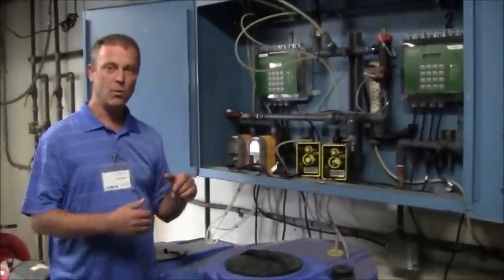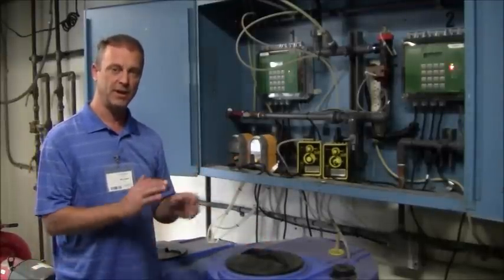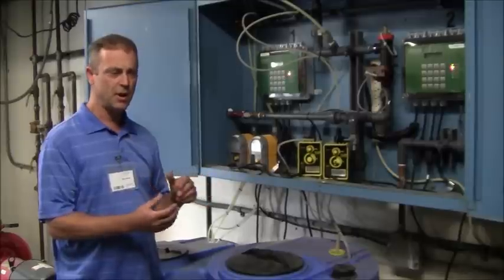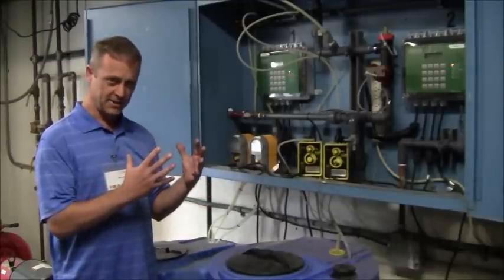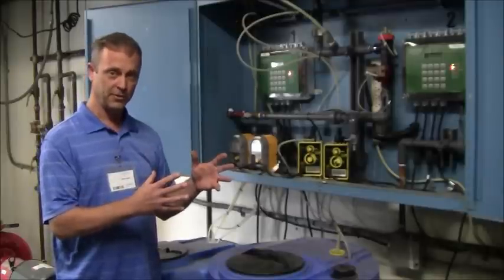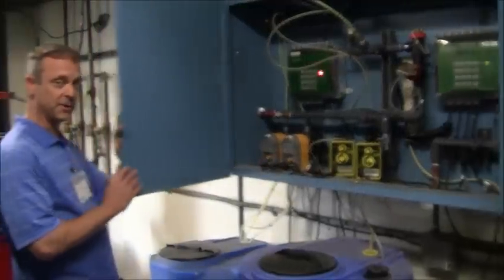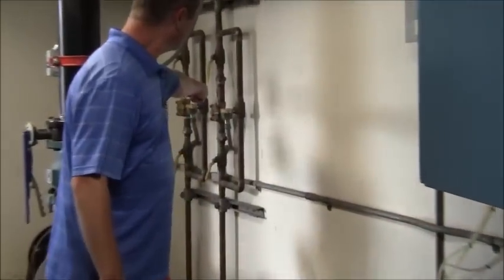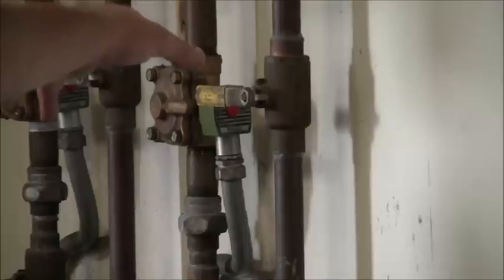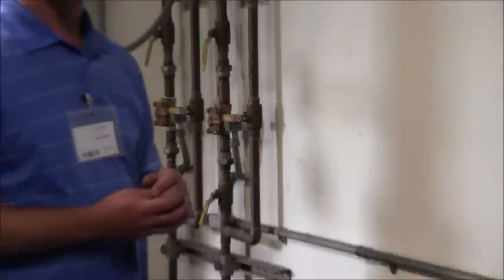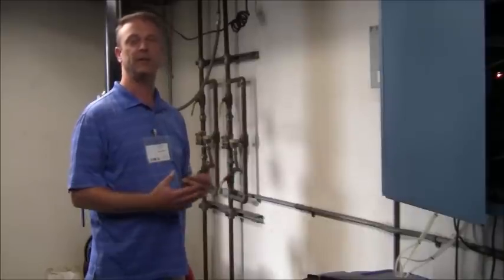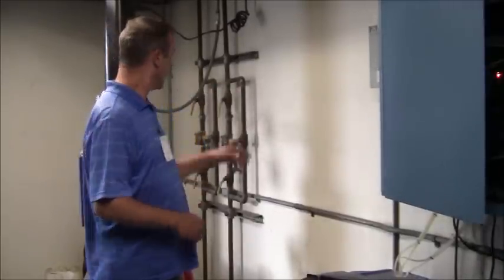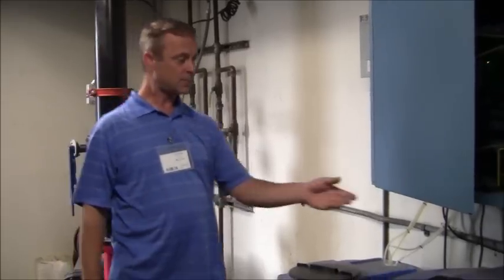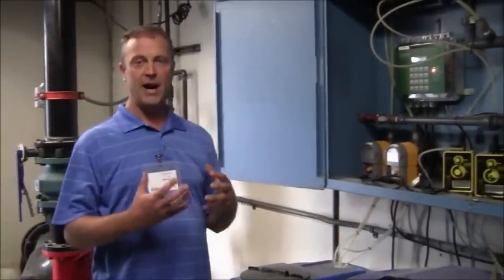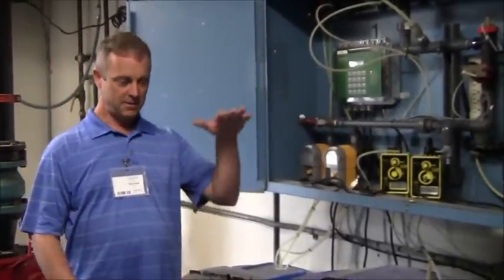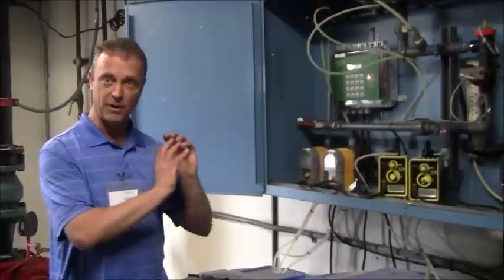And so the controller will feed the inhibitor product based on the programming that you designed it to do. Here we're on a percentage of post-bleed. Basically, the system's going to reach its conductivity set point. It's going to begin a blowdown process. And I'll show you the bleed valve for this system if we can pan over here. And so you typically have an ASCO solenoid bleed valve or some type of diaphragm bleed valve that opens when the controller senses that the conductivity has gotten to its set point. Water is then dumped down the drain, and as that process of high conductivity water is being released down the drain, the tower float inside the cooling tower drops and fresh city water comes in.